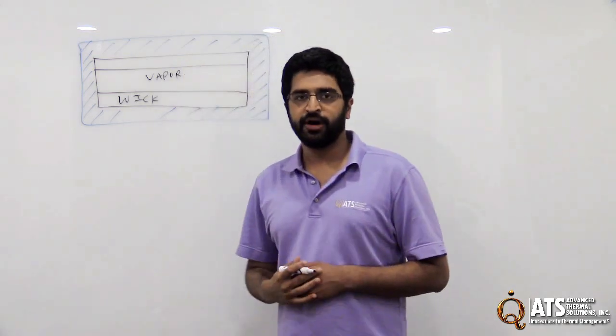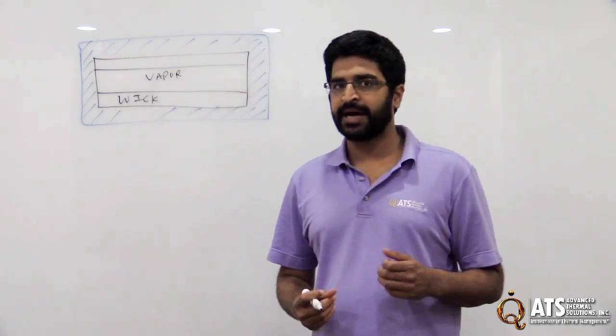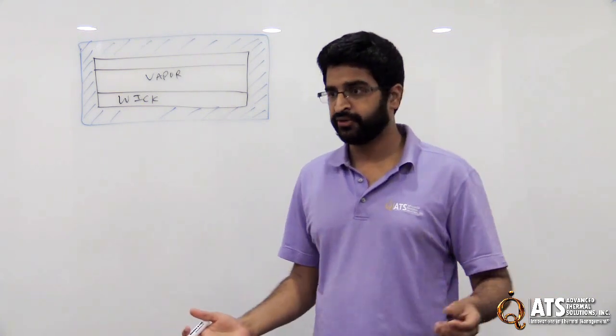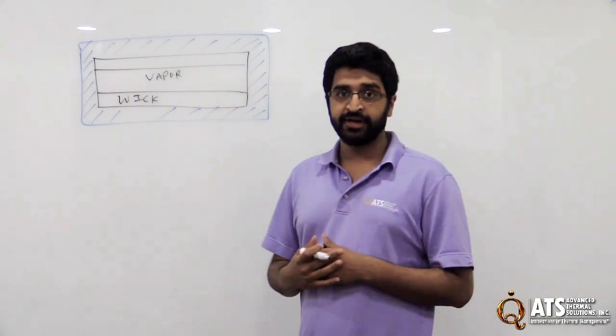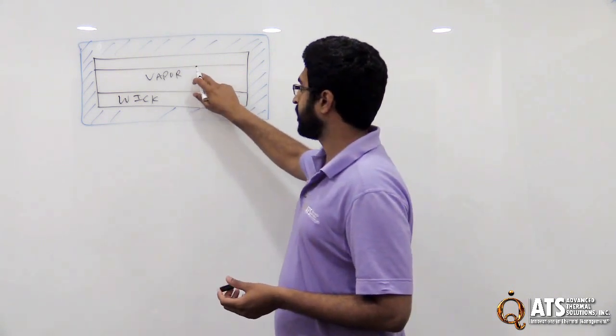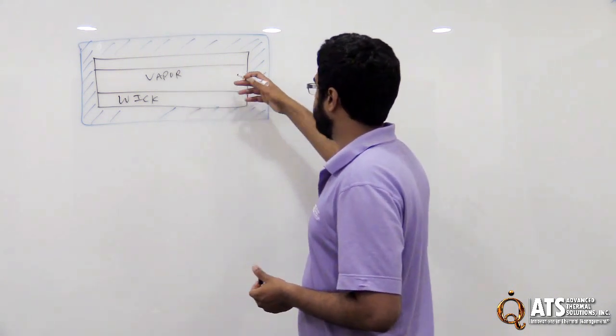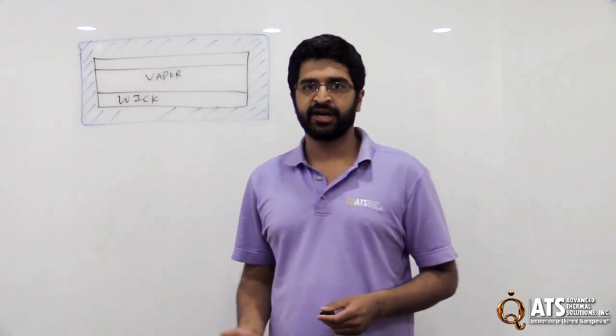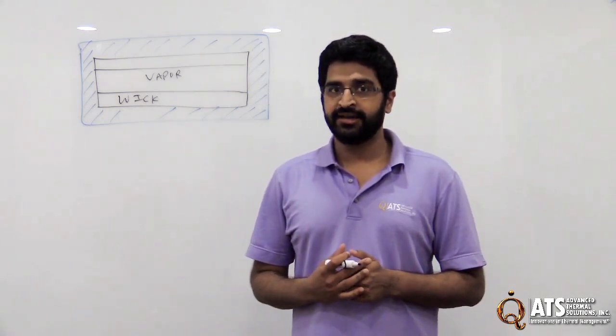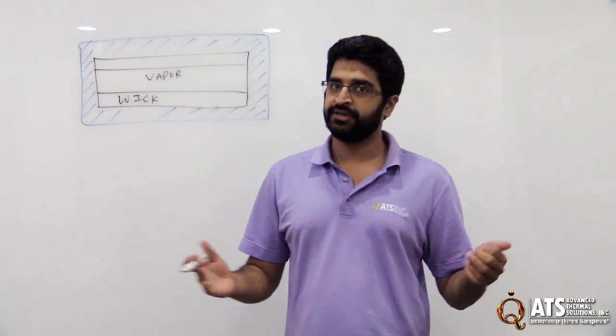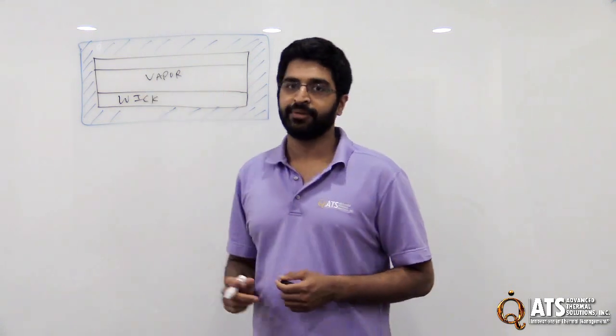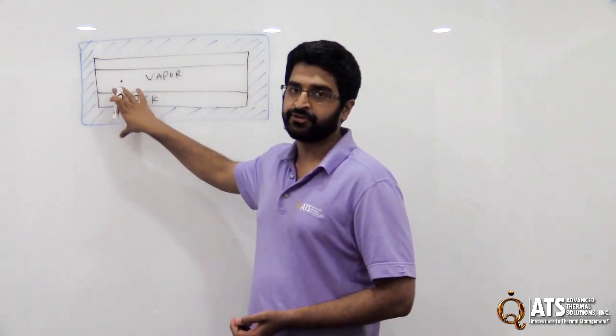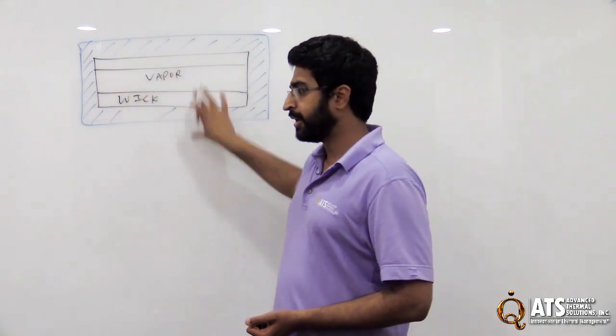So generally when you've heard about how heat pipes have very high conductivity, that's true compared to solid metals. But when you've heard absurd numbers, you're talking about the vapor space here. In this vapor space the thermal conductivity, the effective thermal conductivity is so high that you basically assume that there's no temperature drop across there. But there is a temperature drop associated with the heat transfer going to the vapor space and coming out of there.